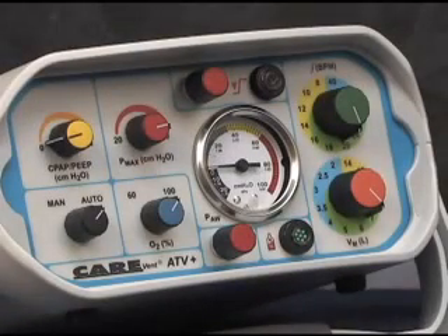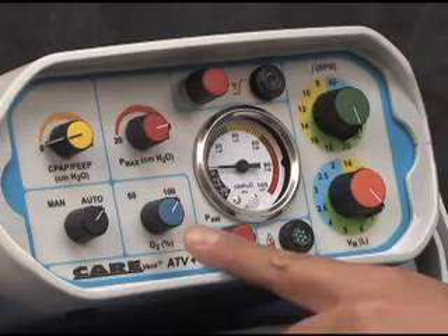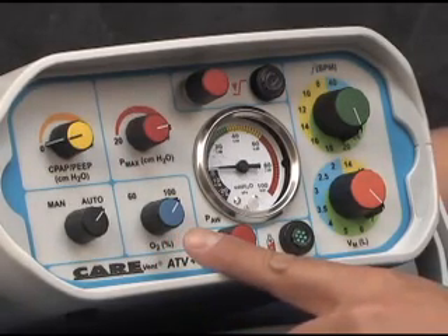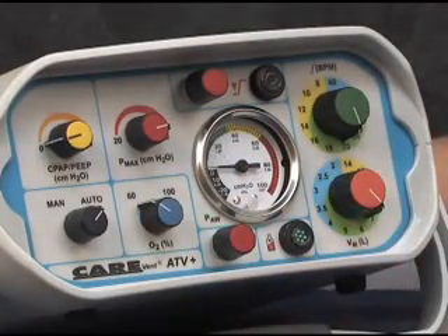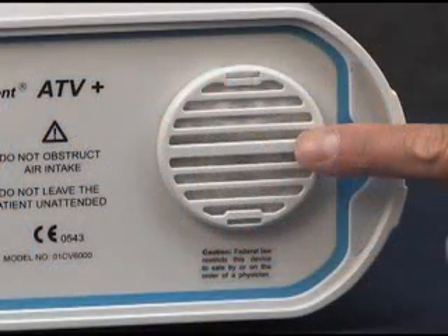To conserve oxygen during long transports or when a patient's respiratory condition requires an oxygen concentration of less than 100%, a two-position oxygen-air mix control is provided. With the air mix control in the 60% oxygen setting, you will hear the sound of ambient air being drawn into the rear of the ventilator during the inspiratory phase. A single patient use snap-in filter is provided to ensure that clean air is drawn into the ventilator when in the air mix mode. The filter should be replaced after each use of the air mix mode to avoid the risk of using a partially occluded or contaminated filter.